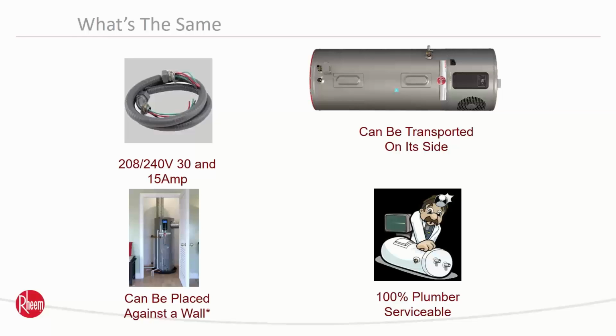And then it's 100% plumber serviceable. You don't have to have a heating license to work on this. Our competitors do require it. They have service ports on their refrigerants, so you do have to go in there and work on their compressors, charge their systems if it gets low, things like that. Our unit is not that way. Like I said before, if anything goes wrong with that top end on that compressor, you take this entire heater out, put a new heater in. That's the way the warranty works, and it's a 10-year warranty.